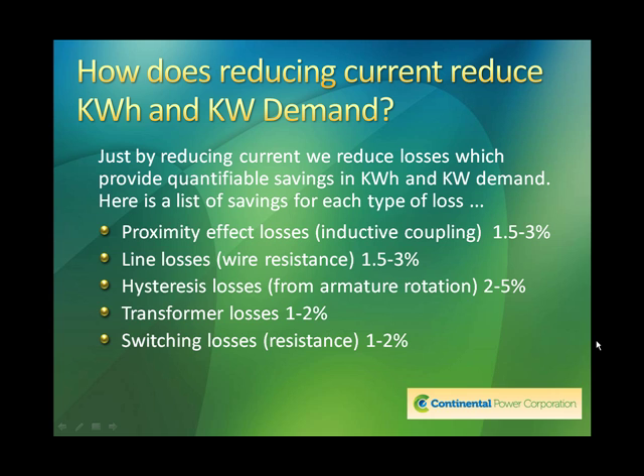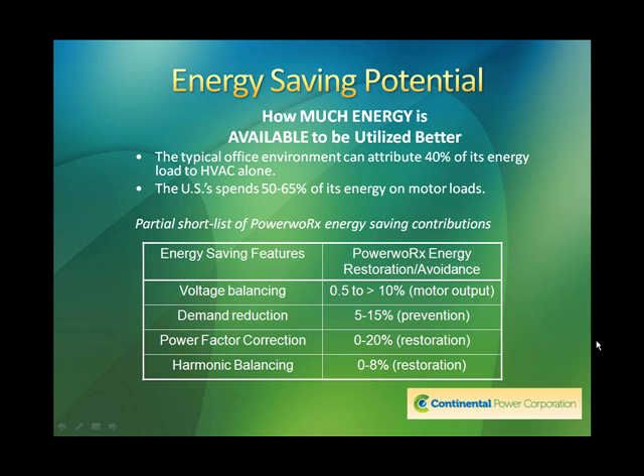Switching losses, this is resistance through relays, through breakers. Again, there's a small amount of resistance through that contact, 1 to 2%. So you add all these up, not one of them is significant, but you add them up and you can see where you can get 5, 6, 7, 8, 10% even savings just by reducing current within the facility.